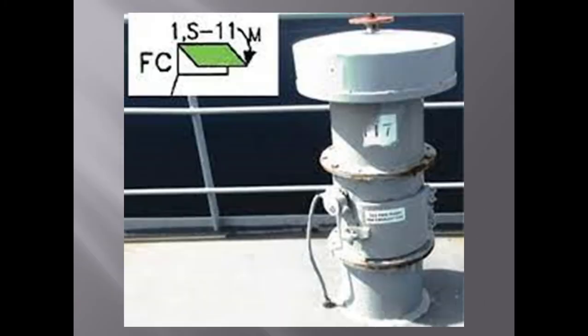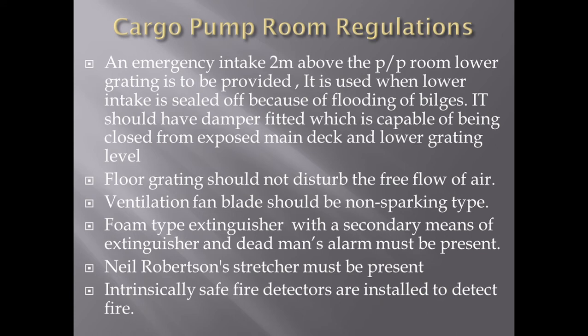We have a damper on the ventilation fan. An emergency intake, two meters above the pump room lower grating, is to be provided. We have a normal suction and also an emergency suction, which is used when the lower intake is sealed off because of flooding of bilges. This emergency suction should have a damper capable of being closed from the exposed main deck and from the lower grating level. The floor grating should not disturb the free flow of air.